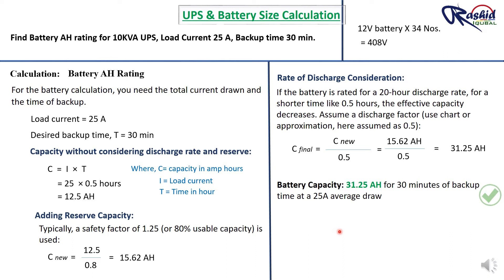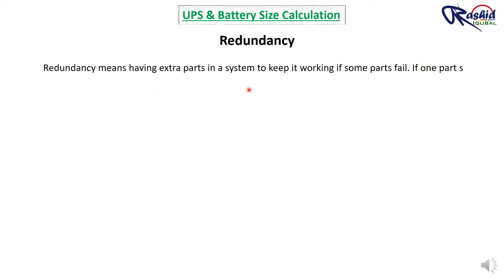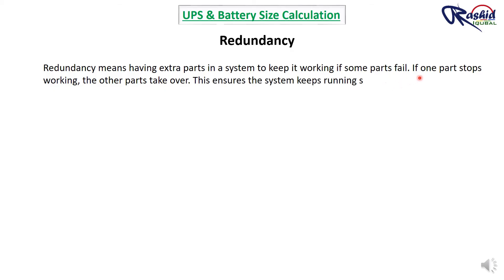So we can go with a 31.25 AH battery rating. One more parameter required when calculating UPS sizing is redundancy. Redundancy means having extra components in a system to keep it working if one part fails — if one part stops working, another takes over, ensuring the system keeps running smoothly. There are three types of redundancy.